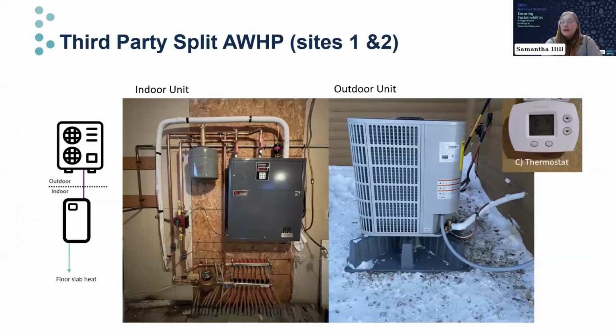This is what the systems look like in real life. So here's what the third-party split systems we installed look like. Inside, there's the indoor unit, which includes that refrigerant-to-water heat exchanger, and that then interfaces with the hydronic heating system. In this case, the manifold at the bottom of the image on the left is what's distributing the water lines throughout the floor in the home to various different zones.